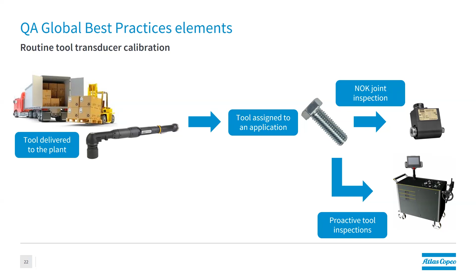If you look at this picture, you'll see there are a lot of transducers. Some are the ones on the tools themselves, and any tool manufacturer will tell you that tool transducers need to be periodically calibrated. A suggestion is usually to do that once a year, but that can change depending on how often the tool is used and which type of application is being used.